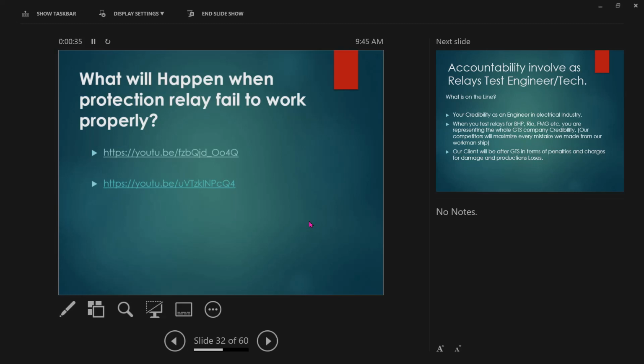It could be the relay is working properly, but when the relay tried to send a trip signal to the trip coil, the trip coil doesn't react to open the circuit. That could be one of the options as well. Or the breaker is working properly and the relay doesn't get the proper signal for the relay to determine that I need to cut off the system for some reason. Yeah. So everything is interconnected. Your CT should be properly connected to the relay to give the relay the right information. Your breaker as well, properly tested. That's why we do maintenance with that one. And the relay. So everything is just working together, giving you the whole picture of what we're doing.